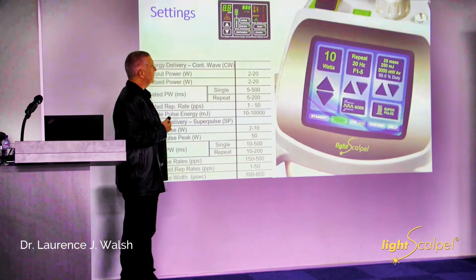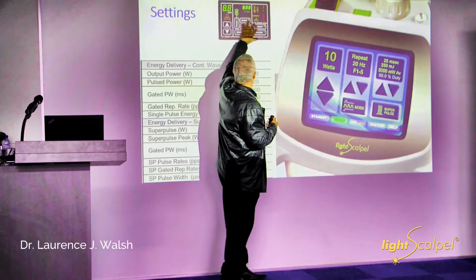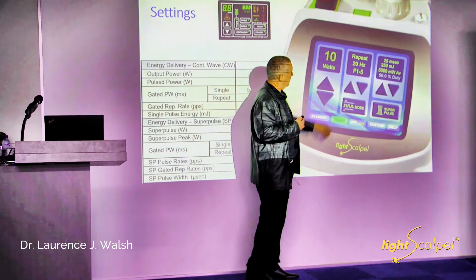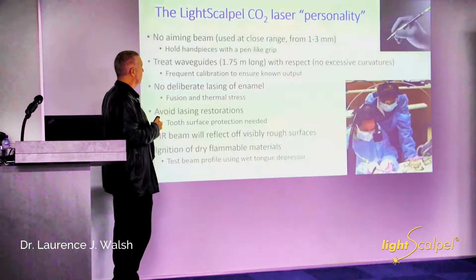Strangely enough, the way the panel is currently laid out is actually reminiscent of the way the panel was 30 years ago — though now it's a touch panel with lots of modes and other features built in. Most importantly, there's the different mode of super pulsing, which really revolutionises the way you use the laser as an ablation tool.